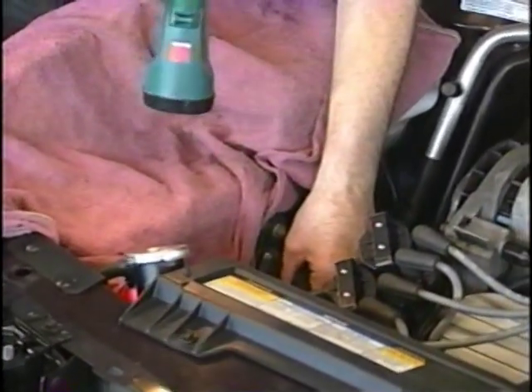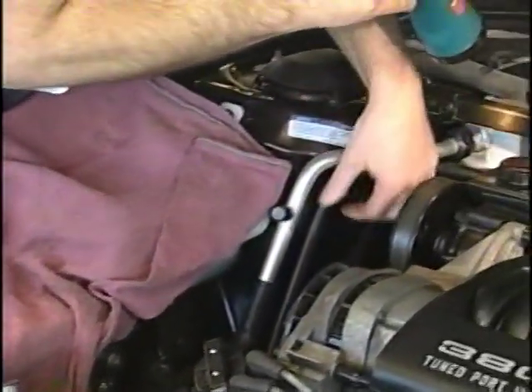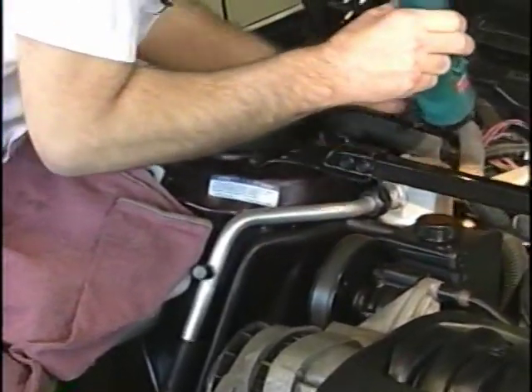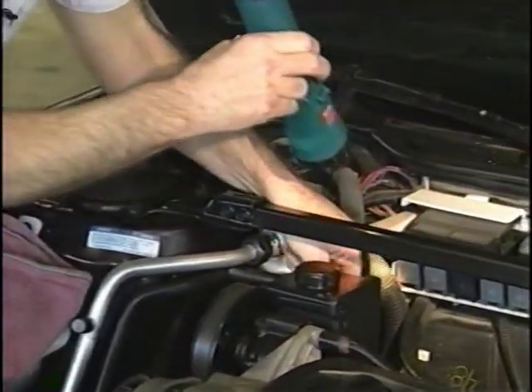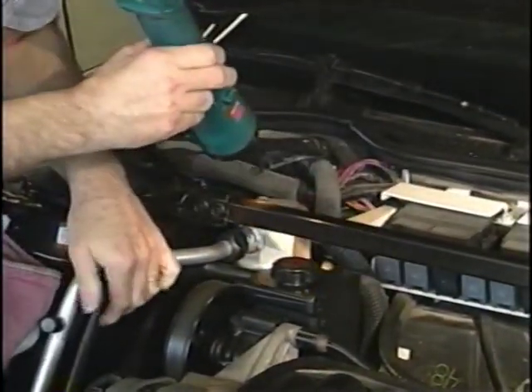And follow the other line on back up to the case where it goes under the core. Look at those fittings. See if it has any signs of damage. Probably one of the most common is low freon, making the compressor sound almost like a bad bearing in it, a real roar type noise on the compressors that run all the time.